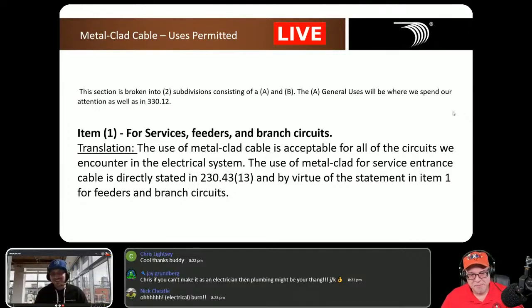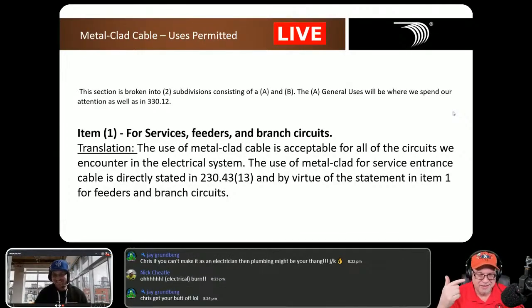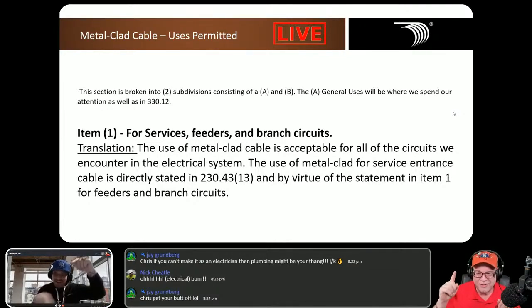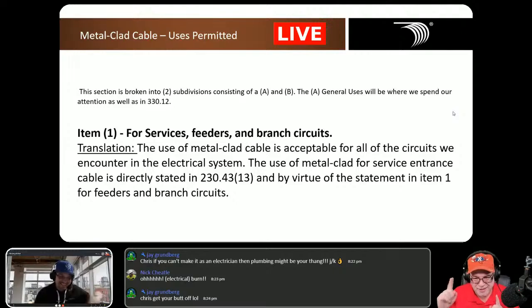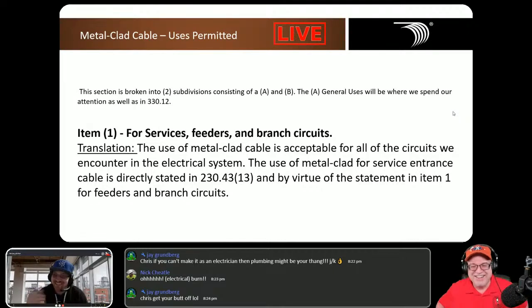Then I was talking to you and you asked, was it PVC jacketed? And I said, well, no. So from your junction box to an exterior panel, you ran that regular little MC, that 2 foot of wire, outside. That 2 foot of cable is a violation of the code because MC cable is only rated for dry locations unless it's PVC jacketed. Once I found that out, I told my buddy to go back and put... liar, you liar, you know daggone well you didn't, he's lying.